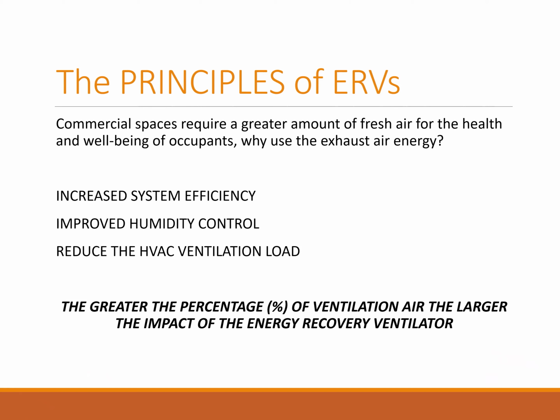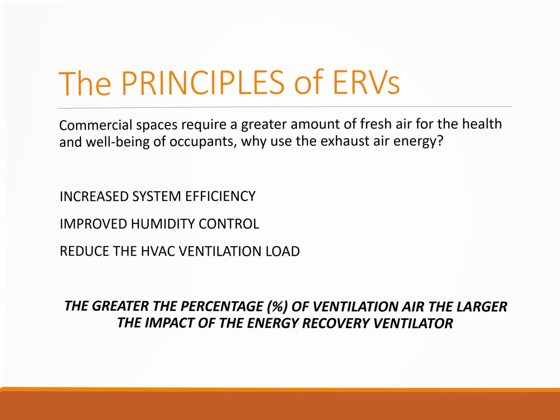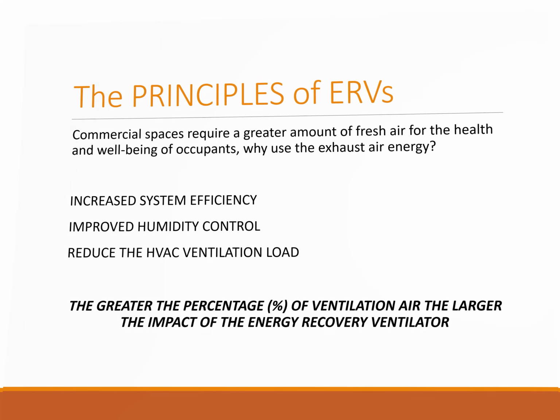MicroMetl ERV products allow for the reduction of HVAC ventilation load. This increases system efficiency and improves humidity control. Commercial spaces are increasingly required to bring in outside air for the improved health and well-being of the occupants in the building. MicroMetl ERVs will help lower the cost of lost energy from outside air by reclaiming energy in the exhaust air and preconditioning or tempering outside air fed into your system.